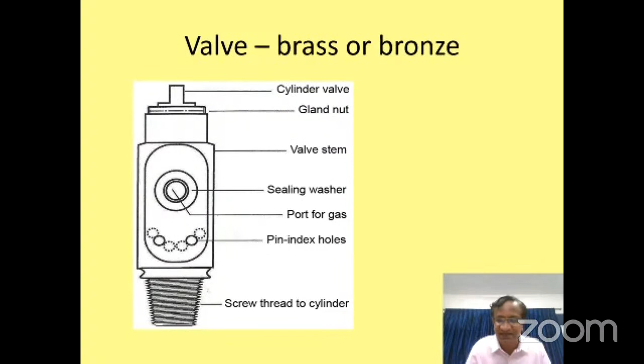This is the cylinder body. The neck is there. The screw is tightened here where we have the oxygen. From here the oxygen will come and go out through this side. And these are the pin index safety systems. And this is the cylinder valve. And this is the gland nut, which we turn like this when we think that there is some leak.